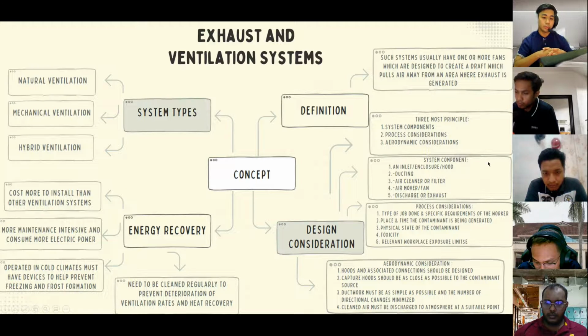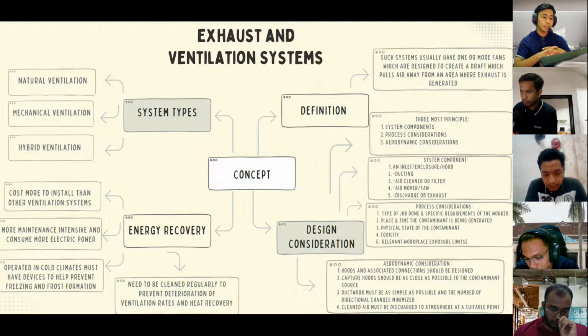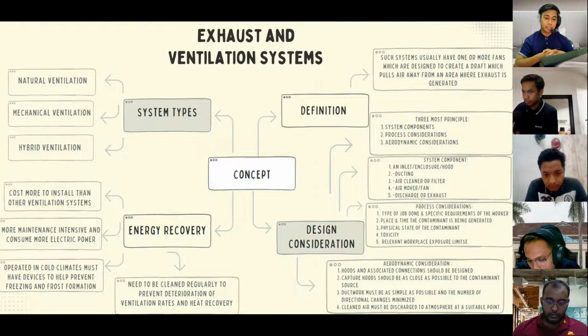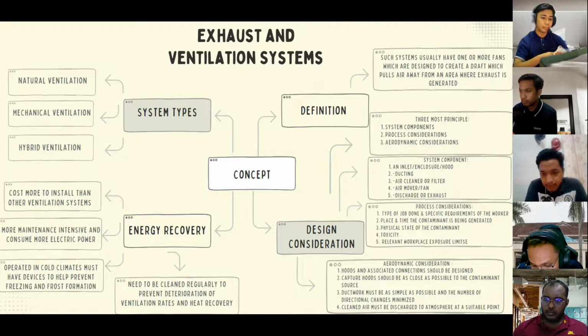Natural ventilation is the use of wind and thermal buoyancy to create air movement in and out without the use of a mechanical system, with the goal of bringing fresh air into the indoor space. The second type is mechanical ventilation, which is forced ventilation. The system supplies the required airflow at a constant rate. Ventilation is supplied by forcing air through the ducting with the use of a fan.